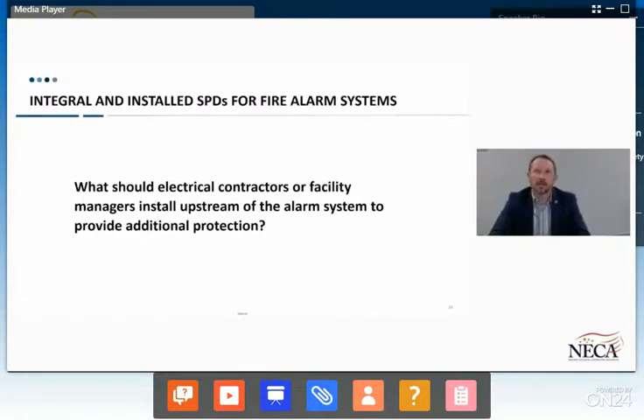One thing I'd like to add is some clarity about why IEEE recommends a cascading protection system. Everything we've heard so far is correct. There's the voltage transformation piece, which is critical, especially in industrial and commercial settings. Just by physics and the nature of the products our industry manufactures, when you have a 480 volt service entrance and you're going all the way down to a 12 volt control, there's no way that 480 volt surge protector is going to step down that transient to the immunity level of the 12 volt circuit. It's not a perfect analogy, but it's like saying I'll put a 500 amp breaker on my service entrance and I'm done with current protection, I don't need anything else. It just doesn't work that way. Transient voltage has to be looked at on an individual, specific level based on what you're trying to protect.